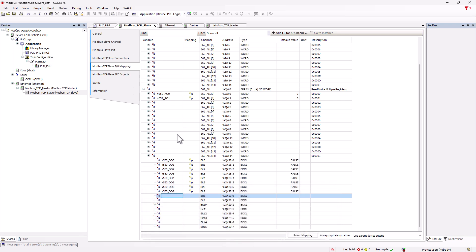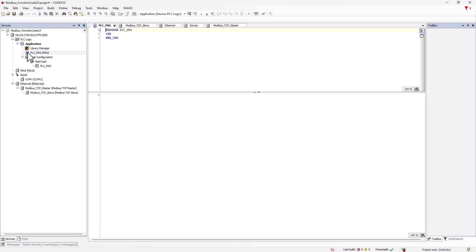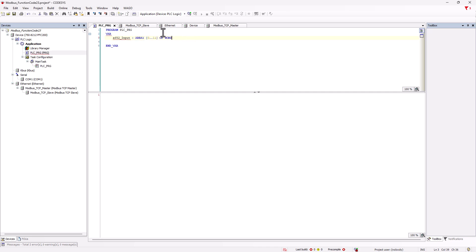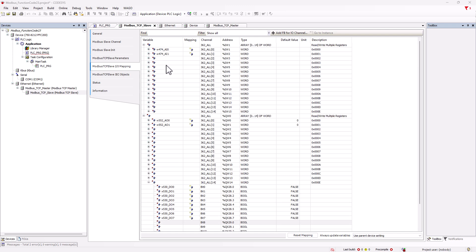The input of the serial interface is in words 2 to 13, thus having a length of 12 words. To read these, you could declare an array of words in the program and call this in the IO mapping on Modbus channel 2.